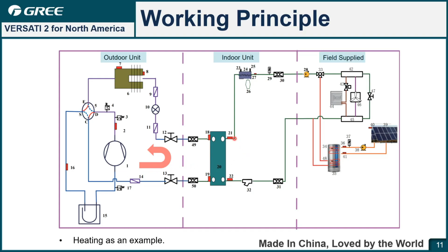At the same time, for the water side, there is a lot of circulation. You can see this is the cold water flowing into the heat exchanger, and then the water will get the heat from the refrigerant, then flow to the water out pipe and flow to here, the e-heater. You can see this is the e-heater, expansion water tank and flow switch, and then flow to the water pump, and then circulate to the 3-way valve.